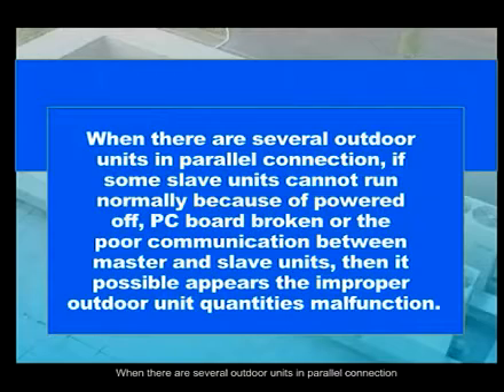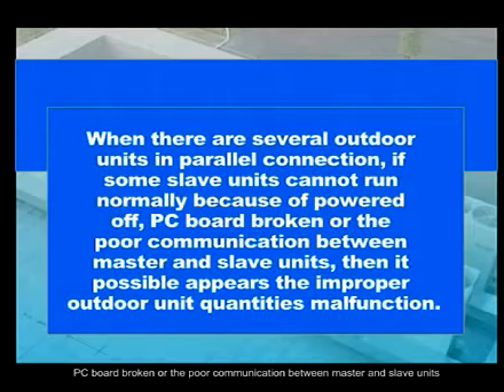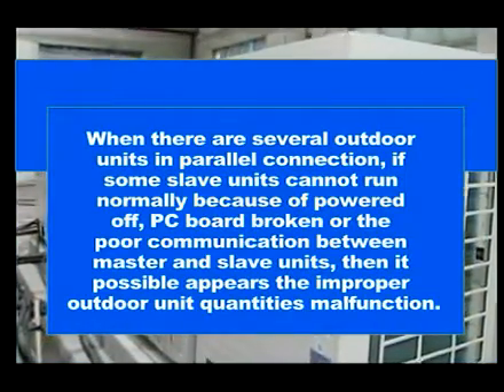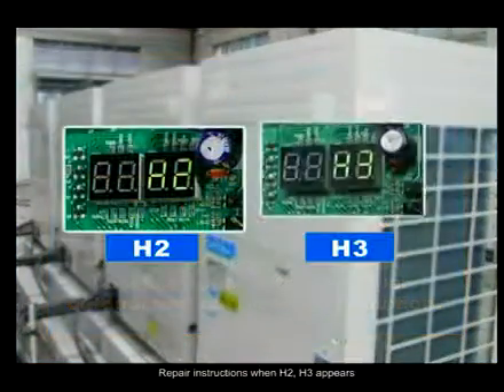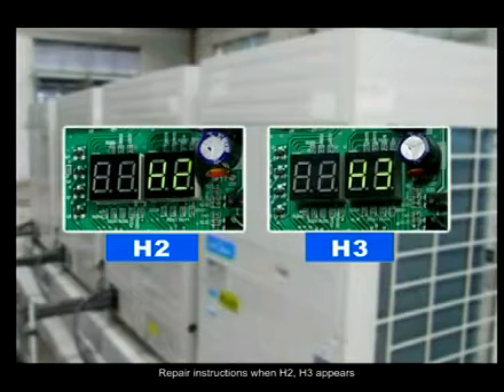When there are several outdoor units in parallel connection, if some slave units cannot run normally because of being powered off, a broken PC board, or poor communication between master and slave units, then the improper outdoor unit quantities malfunction may appear. Repair instructions when H2, H3 appears.